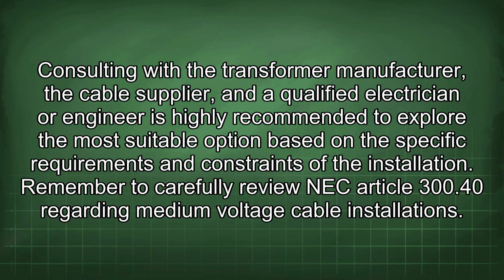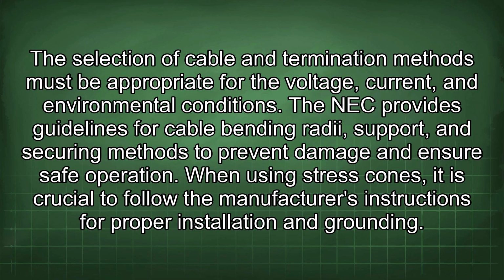Remember to carefully review NEC Article 300.40 regarding medium voltage cable installations. The selection of cable and termination methods must be appropriate for the voltage, current, and environmental conditions. The NEC provides guidelines for cable bending radii, support, and securing methods to prevent damage and ensure safe operation. When using stress cones, it is crucial to follow the manufacturer's instructions for proper installation and grounding.